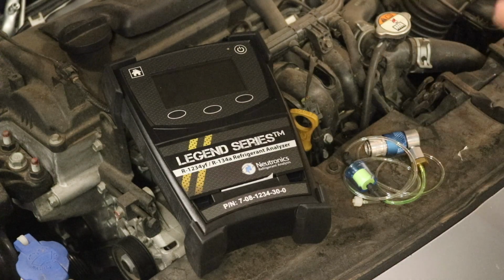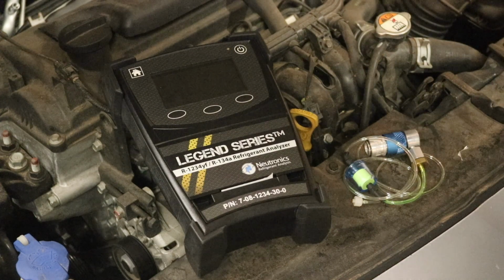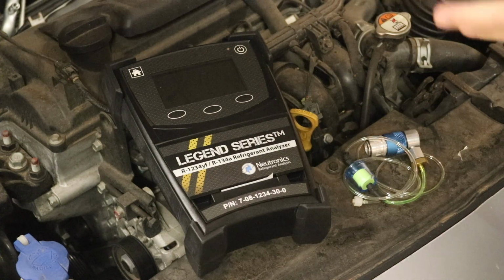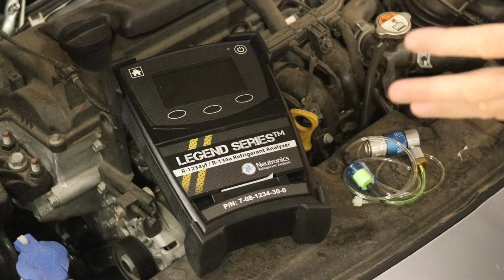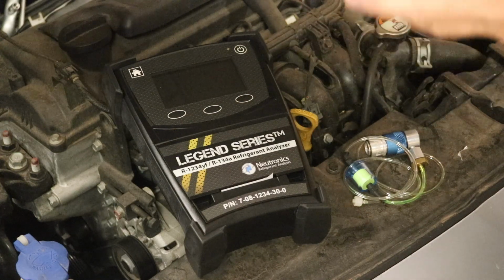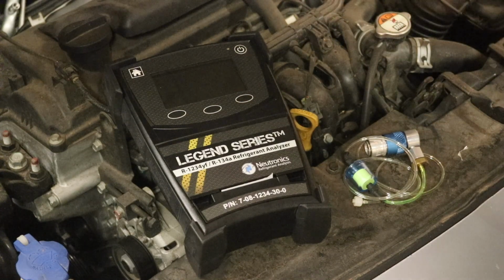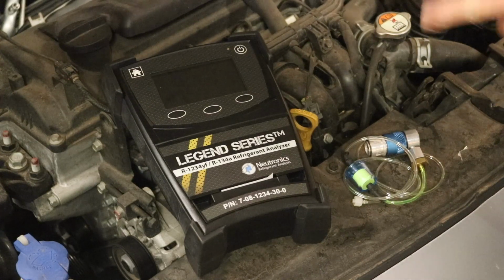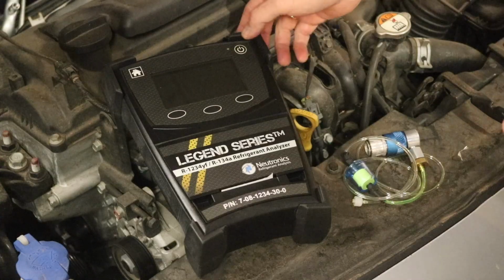Okay, there are 4 stages to the refrigerant analysis. Each of those takes a little less than 30 seconds. So from start to finish, without all the talk, you can do a very accurate refrigerant analysis on your sample in less than 2 minutes. Let's power the machine up. Stage 1.